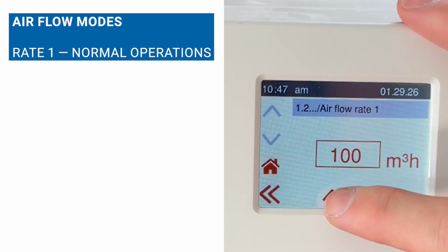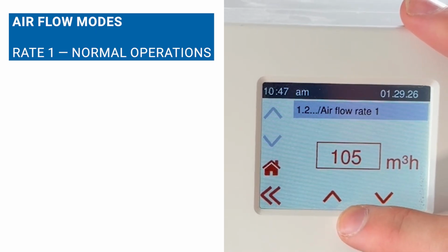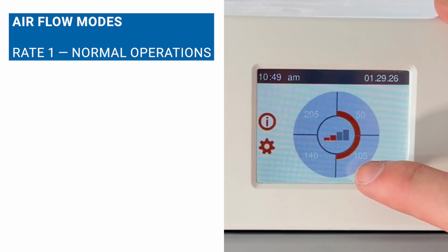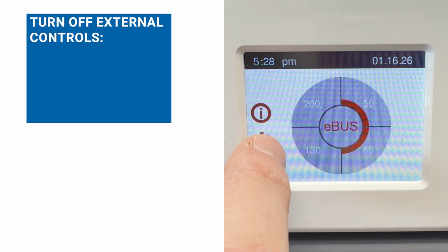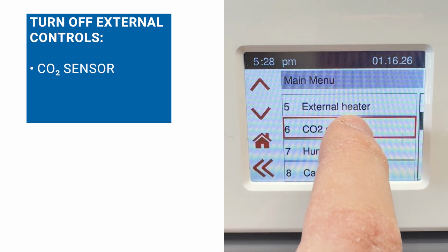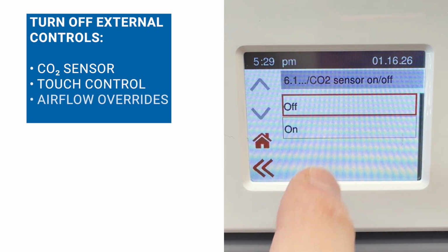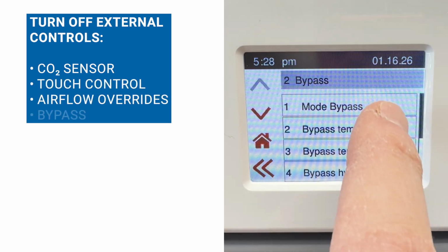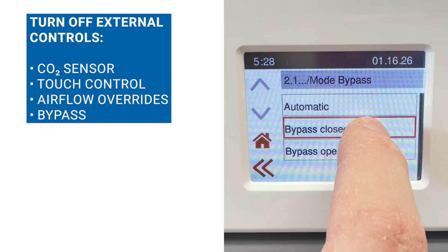Airflow rate 1 is considered normal operations. For use of external controls, the unit should always be set to normal operations. The unit will not boost if it is already manually boosted on the unit, 3rd or 4th quadrants. For commissioning, set the unit to airflow rate 1, normal operations, by touching the bottom right quadrant and turn all external controls off, CO2 sensor, touch control, or anything that would alter the flow rate, as well as the bypass.